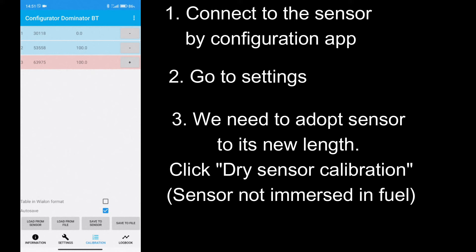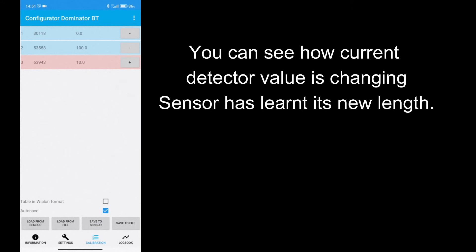It is made using new feature – dry sensor calibration. Just click this button when sensor is not immersed in fuel after you have changed the length of sensor – either it was cut or extended by extra electrodes.